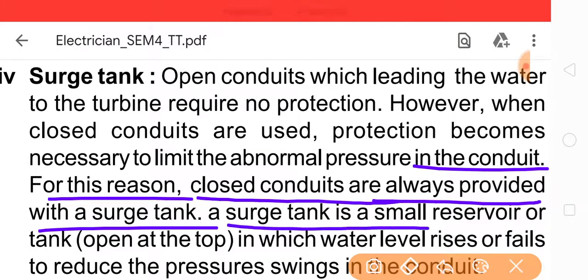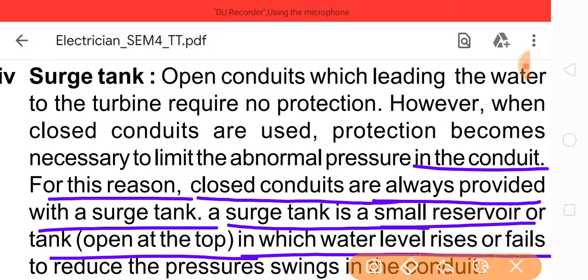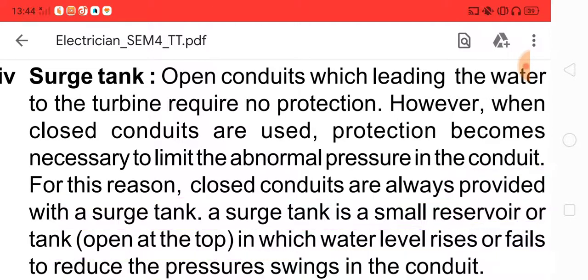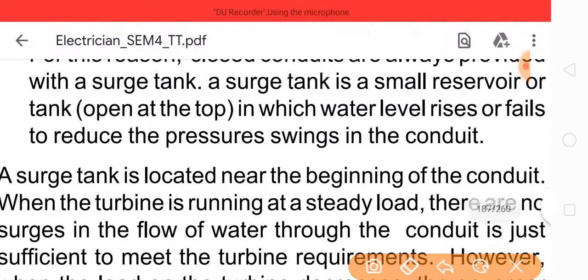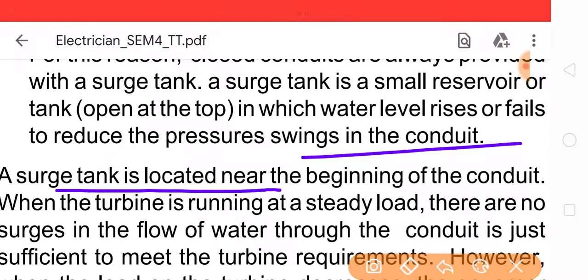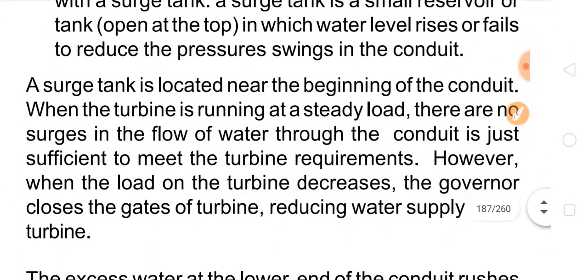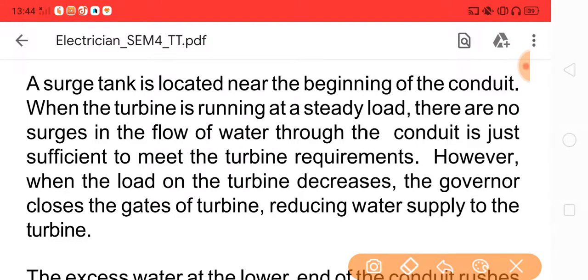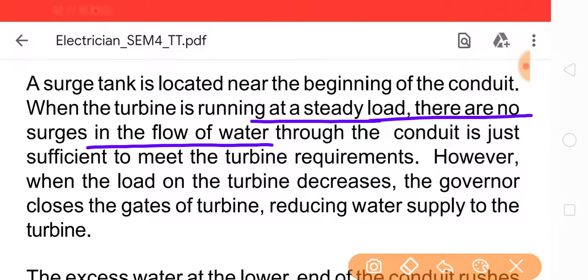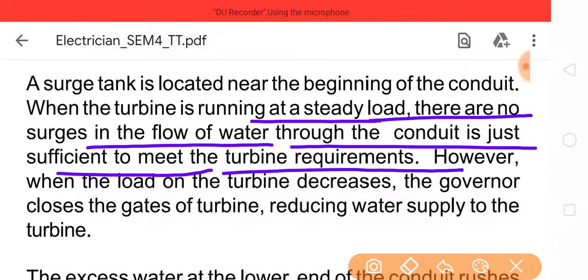A surge tank is a smaller reservoir or tank, open at the top, in which the water level rises or falls to reduce the pressure swings in the conduit. A surge tank is located at the beginning of the conduit. When the turbine is running at a steady load, there are no surges, and the flow of water through the conduit is just sufficient to meet the turbine requirements.